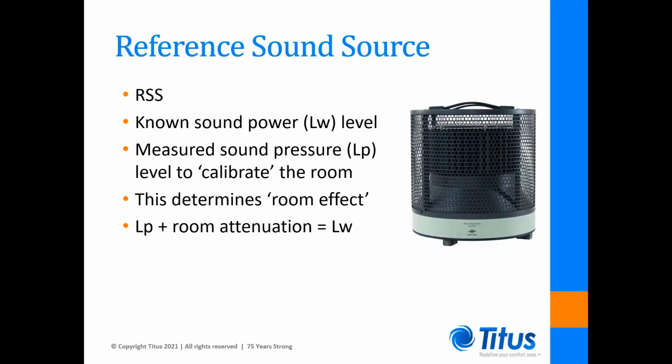We also know that the amount of material and equipment in the room changes the room absorption, so we have to run this test every day to calibrate the room. If anything is added or removed from the room, we must run the RSS again.